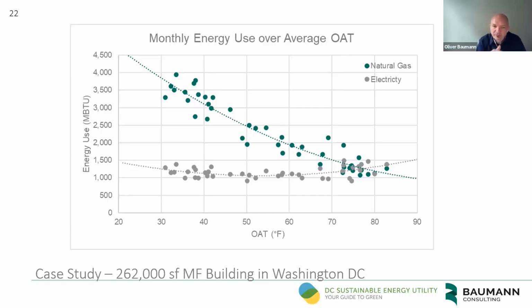Here we see two things. First of all, that the natural gas consumption does not go down to zero and actually plateaus here in months where we would expect no heating demand. So there must be other energy use for natural gas that might indicate inefficiency and an opportunity for energy efficiency measures. And we also see that the slope of the energy use in colder months is steeper than we would like to see. A well-insulated building has a much lower slope, where the impact of the temperature difference between indoor and outdoor is less significant. So that's also an indicator and a confirmation that the building envelope is not very efficient and has opportunity for improvements.